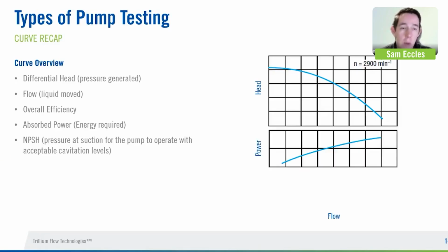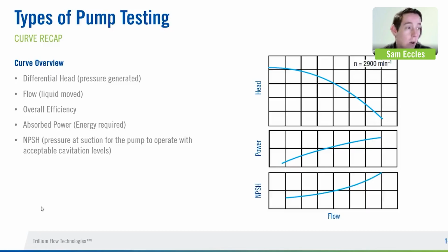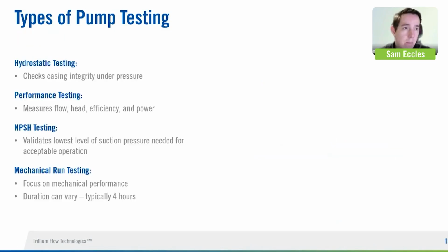We're then also trying to record the power as we go through the flow range and understand, is the efficiency in line with what was sold? Is the motor going to be able to power it at site if there's a difference in product or specific gravity? And then we won't always test for this, but when it's specified, we'll do an NPSH test, which Massimiliano will walk through shortly, and is about proving the level of suction pressure that the pump needs to operate.